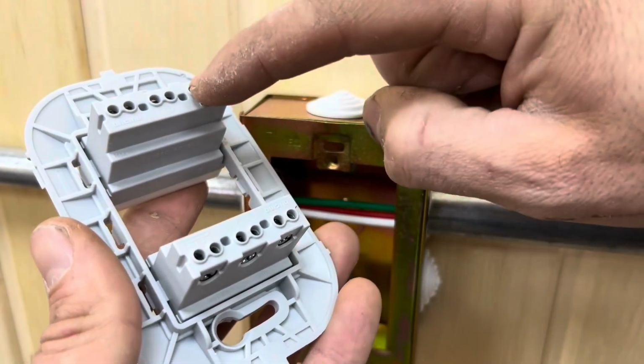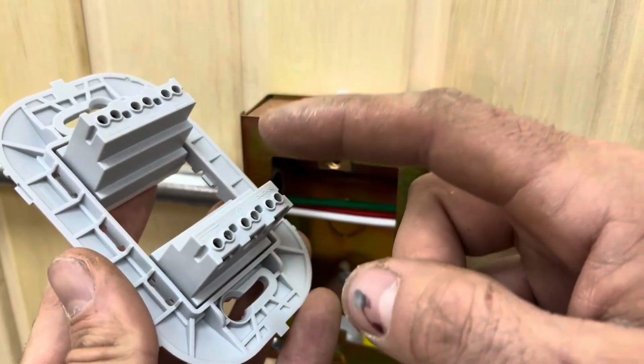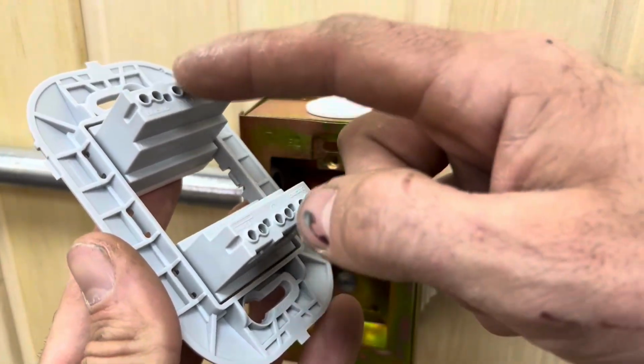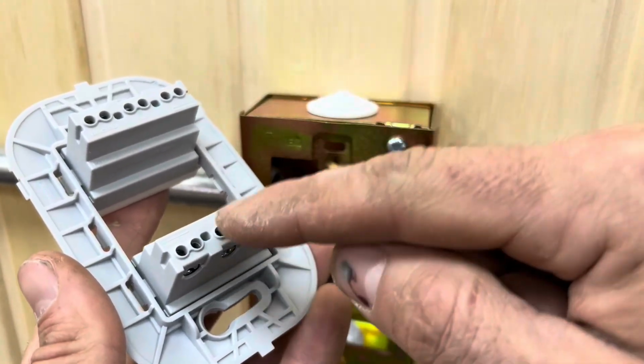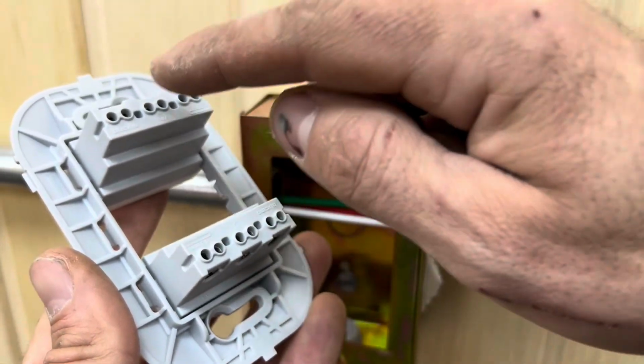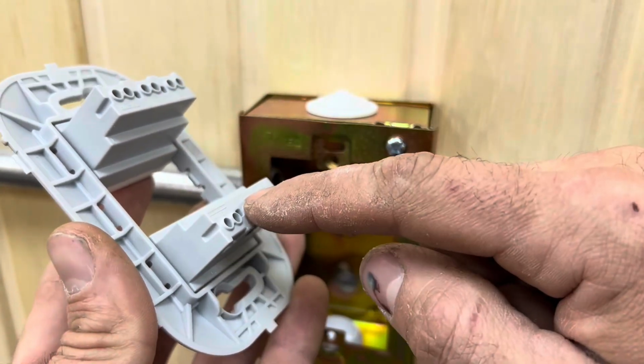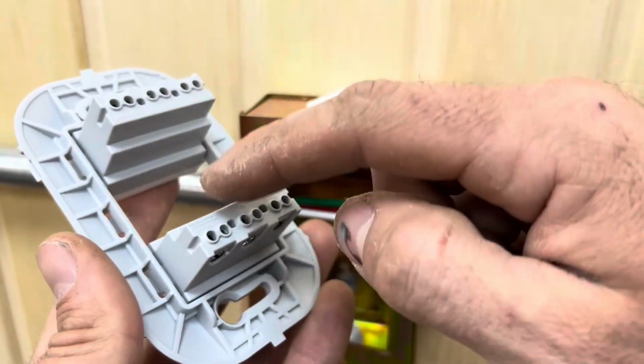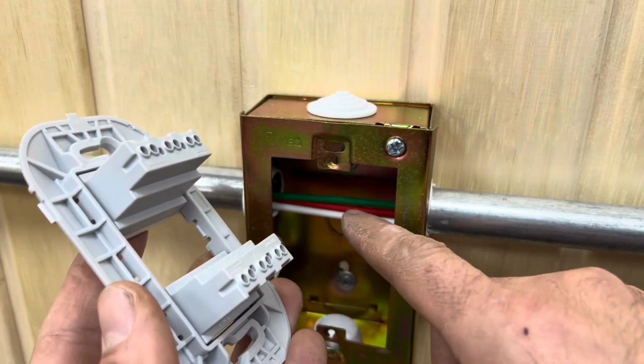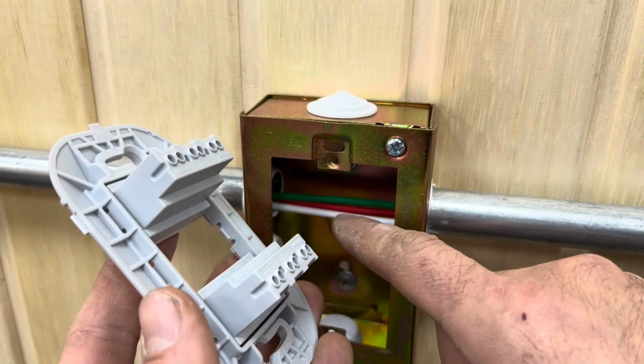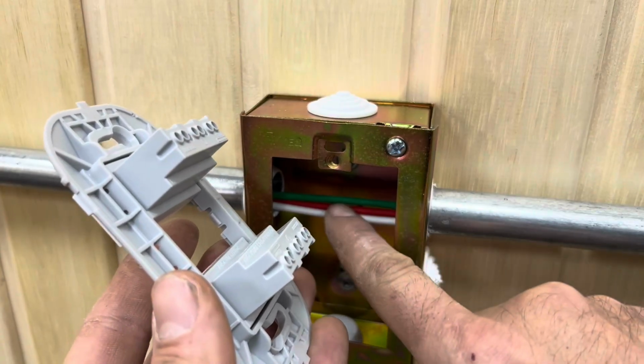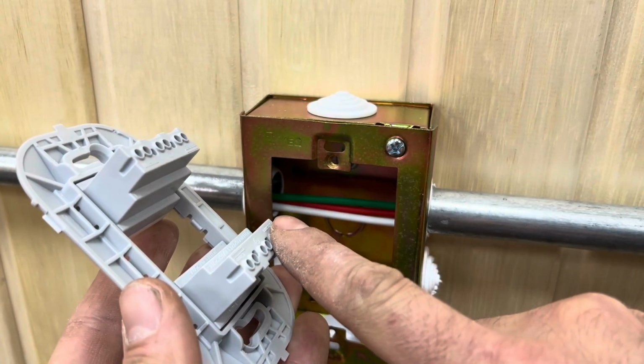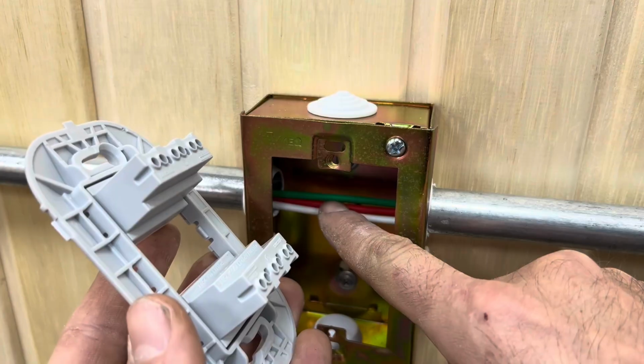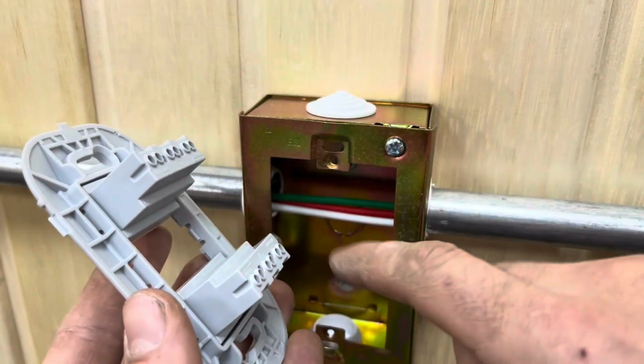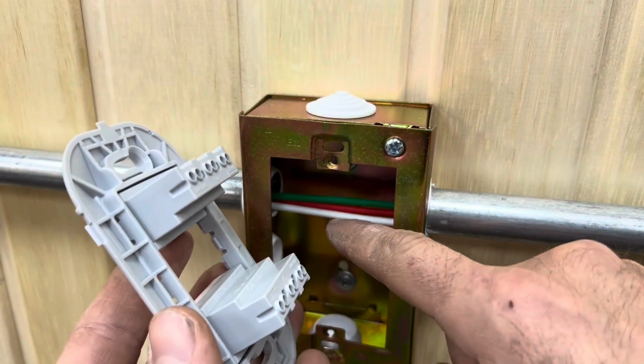1, 2, and 3. The problem with using a jumper is that if we're using both outlets at the same time, the outlet where the jumpers come from can overheat, since it receives the load from both outlets. The best thing for my case is to make a parallel connection. That is, strip these 3 wires here, run a wire over here, and then from this same point, run another wire over here. So there will be 3 jumpers, 3 here and 3 over there.